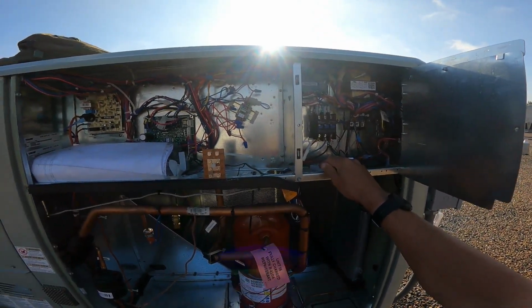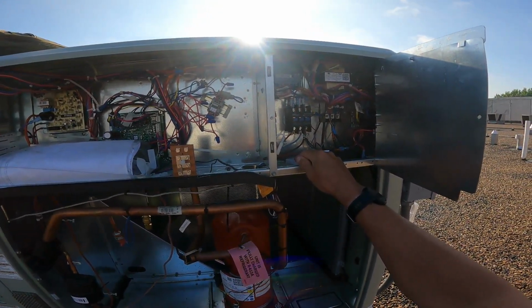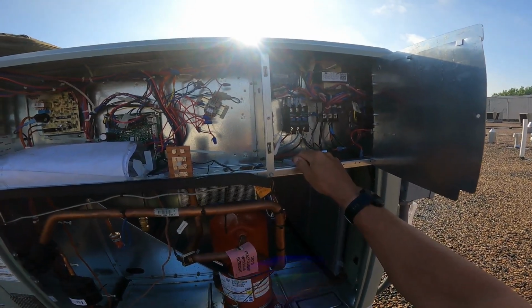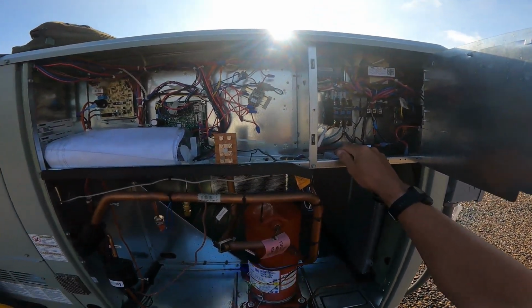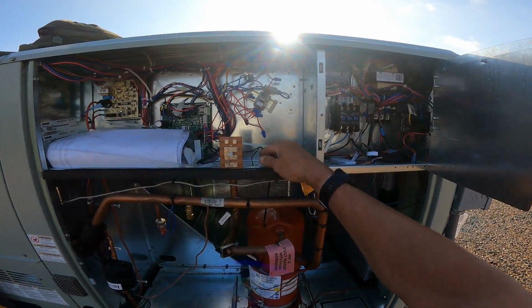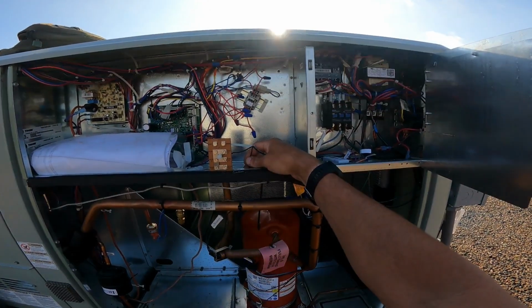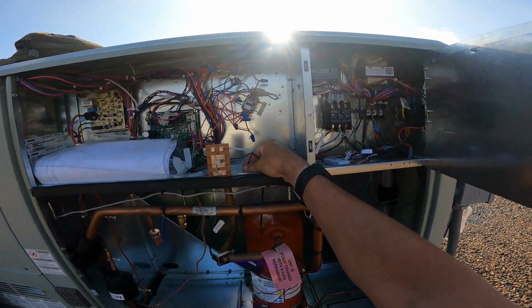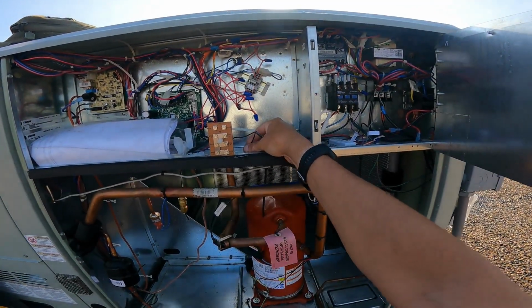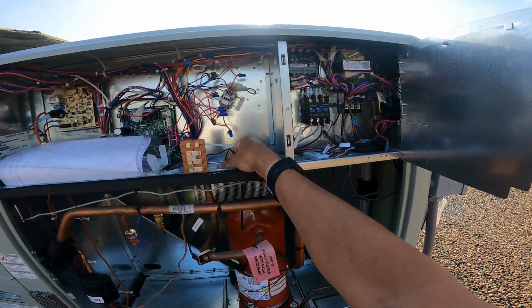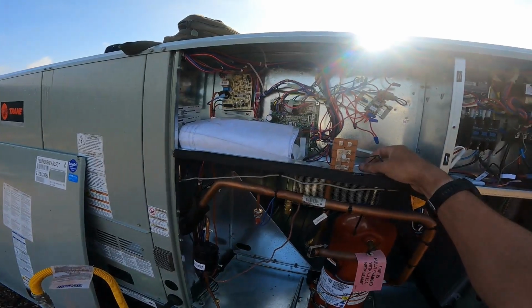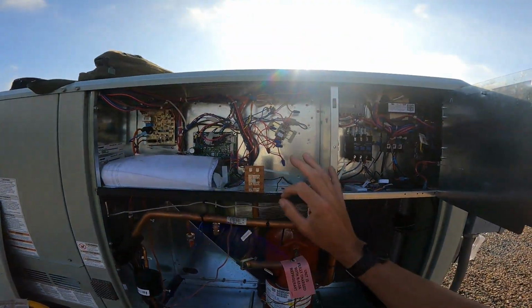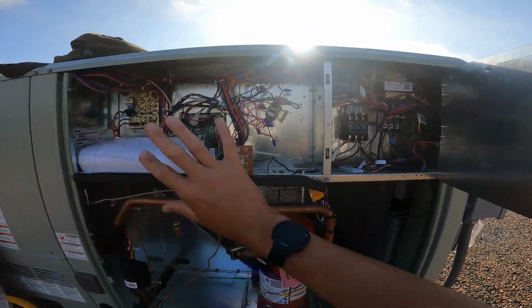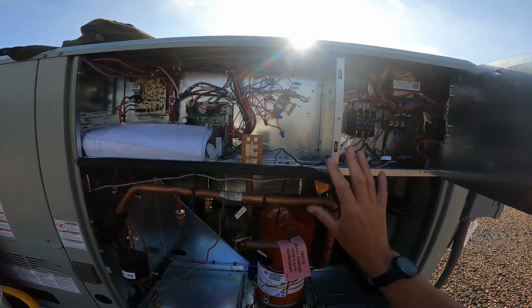We're gonna run this 24 and common directly to the transformer. That's the easiest way, not necessarily the best. Last resort, you run your common to a ground. You can even run a neutral to a ground in a 115 volt application as a last resort to get it going, not permanent.